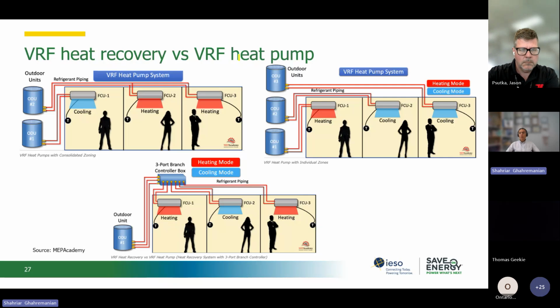We have two types of VRF systems. The first is VRF heat pumps. Basically, it means that each unit, for example, let's say this is unit one, is connected to outdoor unit number one, actually. And then this person can control unit one, either heating or cooling. This becomes similar to a ductless split system. And then unit two serves zone two and zone three actually, but zones two and three need to operate in the same mode. For example, in this case, we have both of them on heating actually. So if one of them was heating and the other one was cooling, then we would need to add an extra outdoor unit to that actually. Then each of these zones becomes independent.